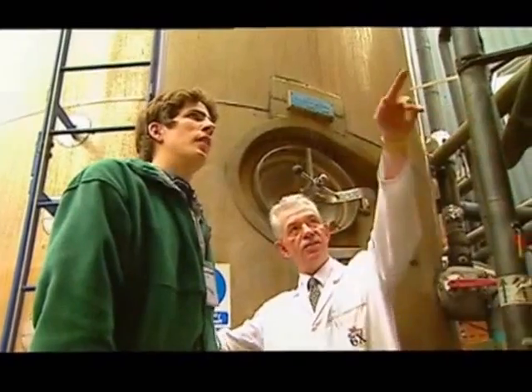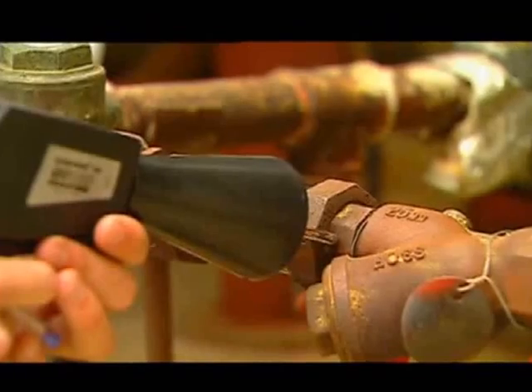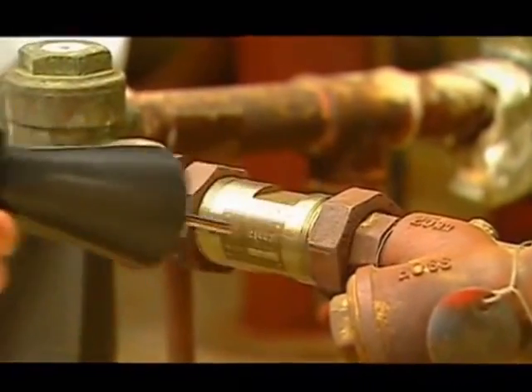Because we're a day operation, we start the boilers at 4:30, 5 o'clock in the morning, and they're off all night. So we get cooling down in the pipes and we experience a tremendous amount of water hammer. Since the Gem traps have been in, that's much improved — in fact, I'd go as far as saying you don't even notice it.